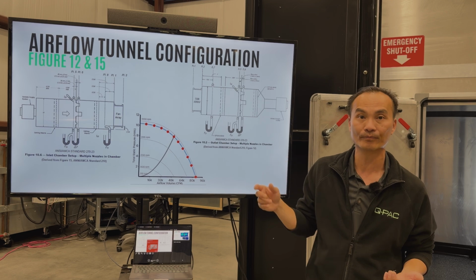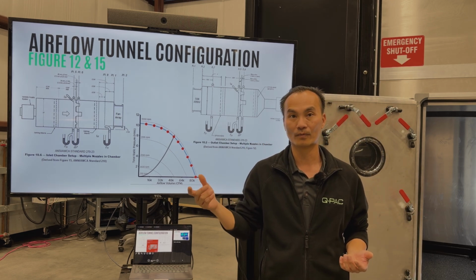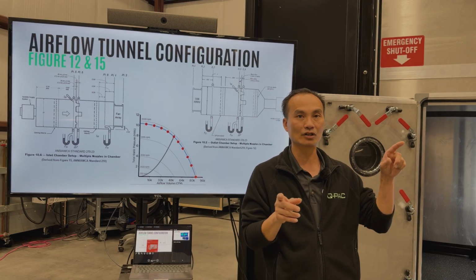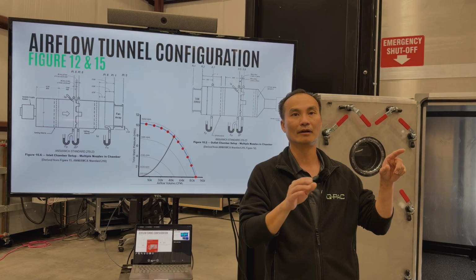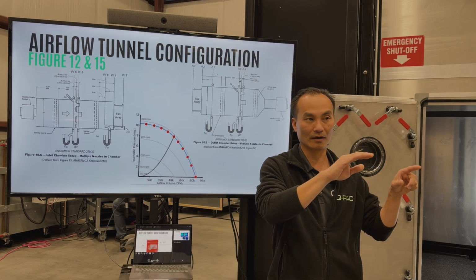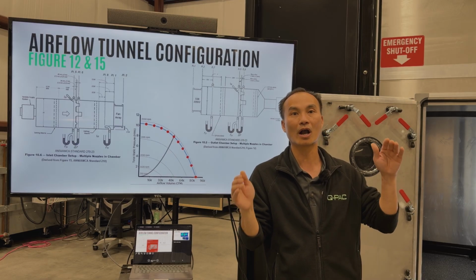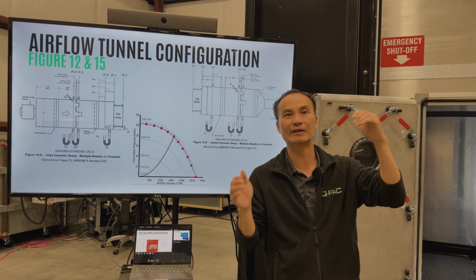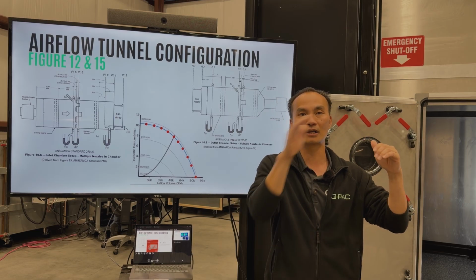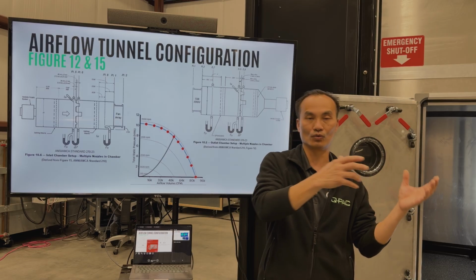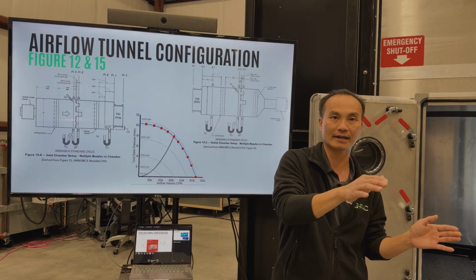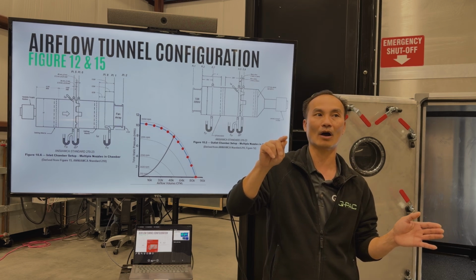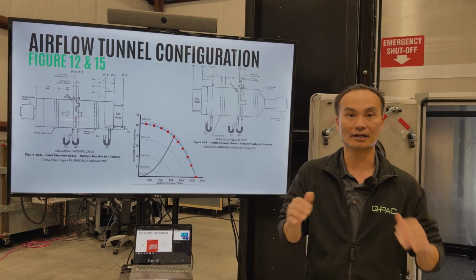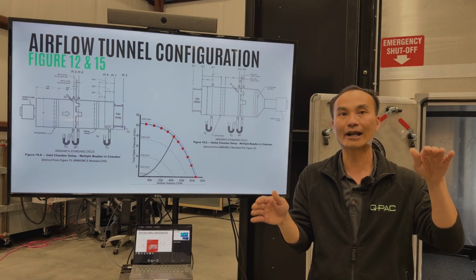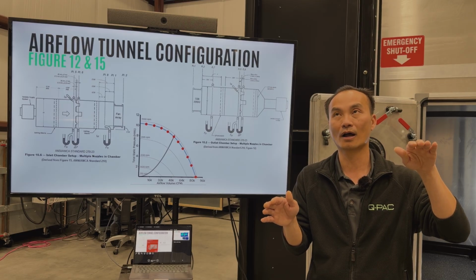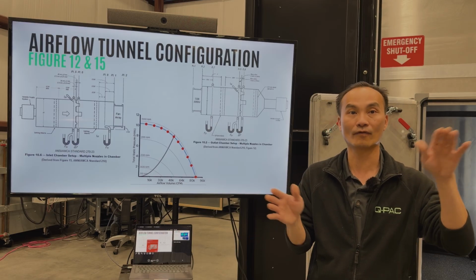design is important. At the development level, by precisely controlling and automating this whole system, we have the ability to build in an automatic test process that allows us to cut almost 80 to 90, like 80%, of the amount of testing that we require to hit a certain point, because we're using software and data to extrapolate the data. Then we need to test only a few verification points in order to make sure that the system predicts and extrapolates accurately enough to meet AMCA accreditation or certification.